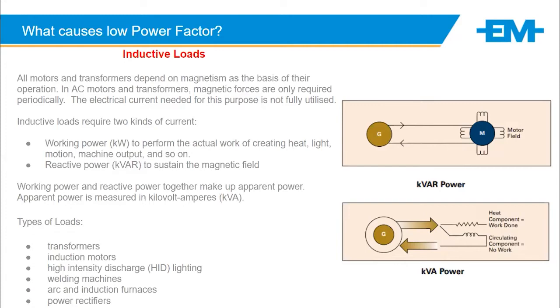Okay. So what type of loads create this demand or this magnetic field? Induction motors, HID, high intensity discharge light, welding machines, arc induction furnaces, power rectifiers. So this is not a new concept. It's always been there, but the utilities are taking advantage of this. They obviously have to make their money back and claw back your inefficiency. And they do that by charging kVA charges.